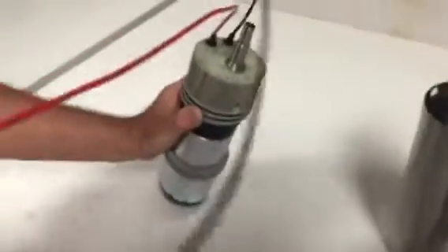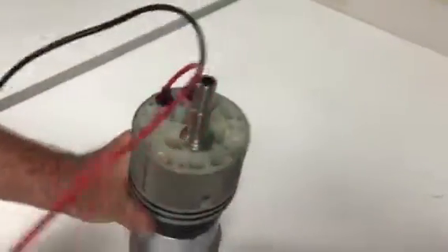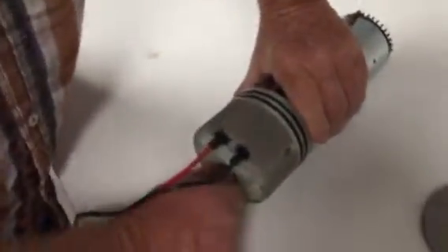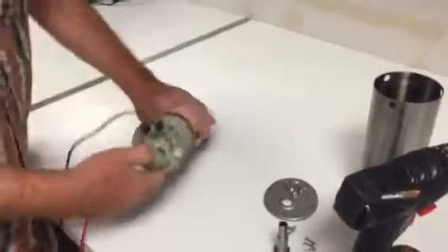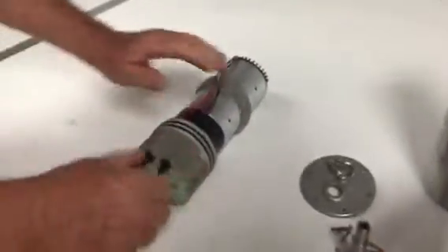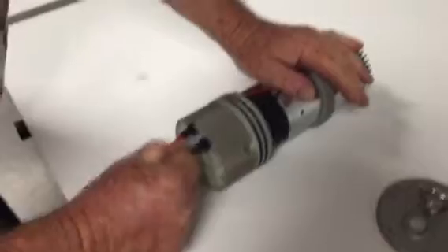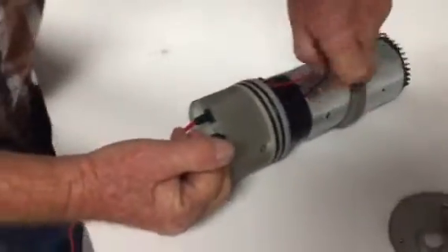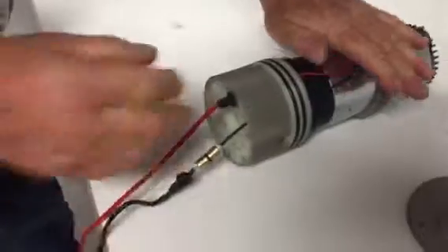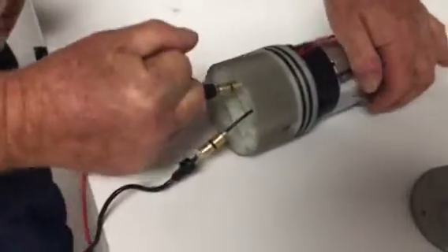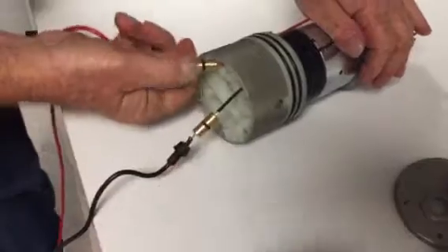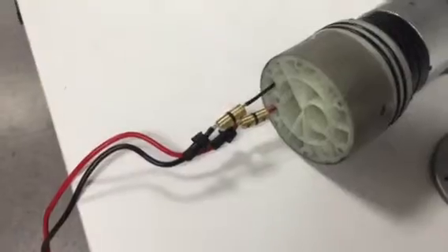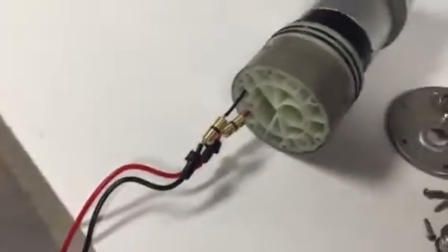We've removed the 7 screws that hold the lid to the top of the pump. Now we're removing the outlet nipple. It just pulls out by hand. Next, we're going to remove the 2 wires, black and red. You pull out. What you will find is the O-ring socket here which secures the cables into the housing. Once that is removed, we can proceed.